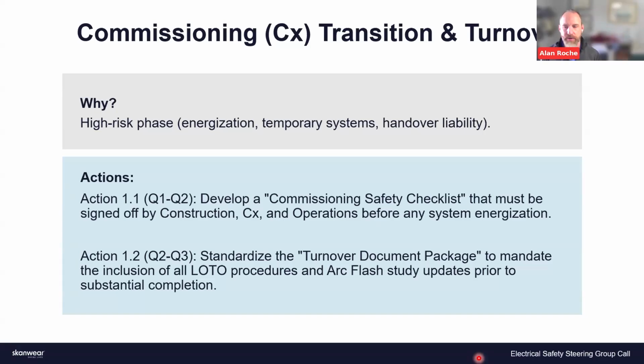So that side-by-side operations during level 4 and level 5 testing is key for the operations team. And that final turnover, it's a process, not a single event - just like commissioning is a process, not an event. Commissioning isn't just getting out there and doing the testing; it's everything from design review all the way to turnover to operations.